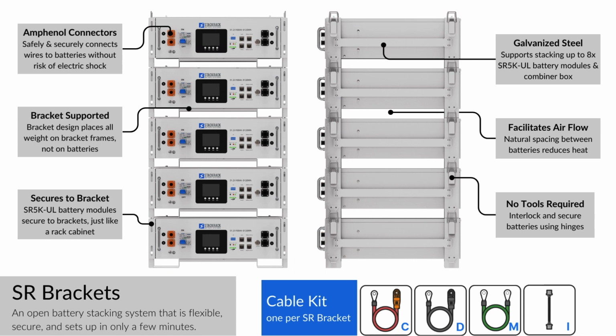What really pairs well with the SNA 6000 is our brackets. The brackets allow for a very cost-effective way to stack and build up a battery bank while securing the batteries safely. Some of the advanced features that the brackets offer: no weight is sitting on the batteries. Through the design of the brackets, it's distributing the forces from bracket to bracket, and you're securing the batteries to the bracket using the rack mount holes in the front. The natural gap between the different brackets facilitates airflow. The brackets are made of galvanized steel. It's designed to support up to 8 batteries in terms of weight. The way that these secure and interconnect using these latches, you don't have to use any tools to secure these batteries. With each bracket, we send a cable kit that includes power cables, grounding, and communication cables.